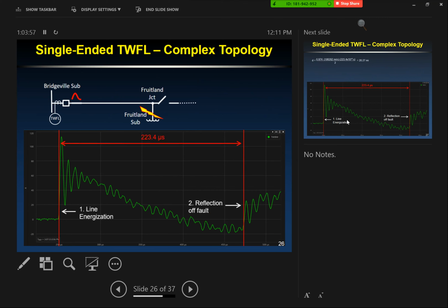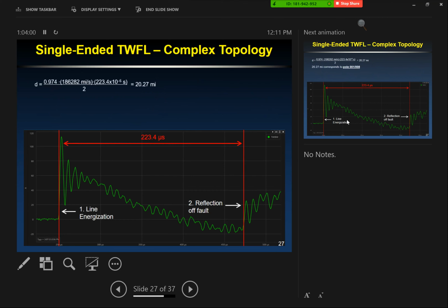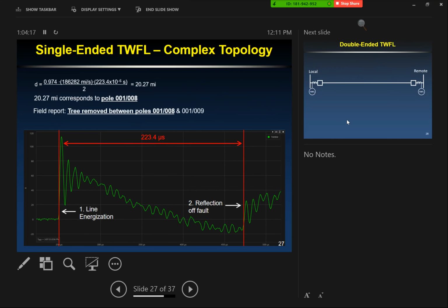So, and we could look at the time difference, and we can just use that same formula up here. Relative speed of light times your speed of light in miles per second times time divided by 2, 20.27 miles. And using our GIS system I was talking about before, that corresponds to pole 1/8, and that's the fault location that we gave. Field report came back, tree removed between poles 1/8 and 1/9. So it's nice to give a perfect fault location for a little rinky-dink 60 kV line where you have a fault way out on a tap. Using conventional methods, I'd be happy to just tell them it's somewhere out on that tap, go look at it.